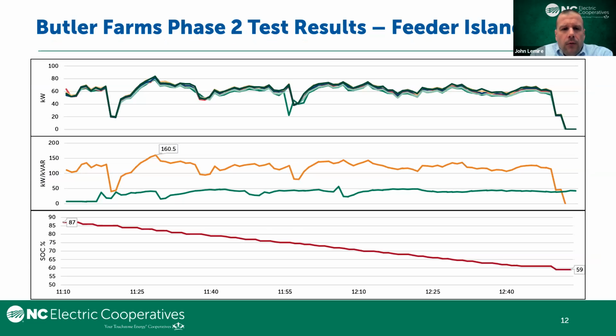At Butler Farms, when we were testing, we built the project out in multiple phases. During our phase 2 testing, which is supporting the farm on the microgrid but also going out on the distribution line and supporting 28 homes within our isolation boundary, we had some issues come up. And so my fourth lesson is around the reference voltage that you're using for your island operation.